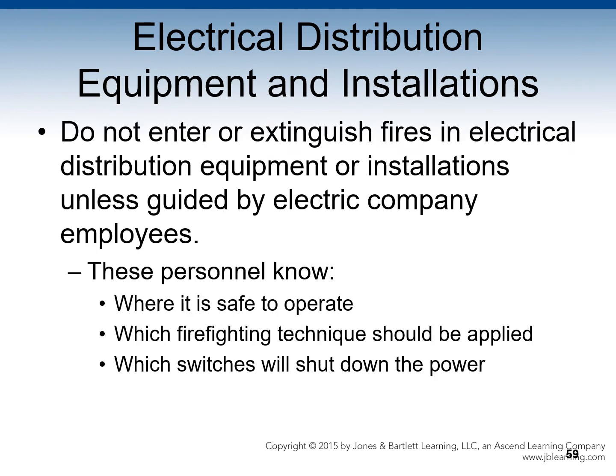As a general rule, firefighters should not enter or extinguish fires in electrical distribution equipment or installations unless guided by electrical company employees. These personnel are trained and know where it is safe to operate and which firefighting technique should be applied. They know which switches to throw and which switches to shut down the power. Once the power is shut down, a Class C fire reverts to Class A, B, D, or K.